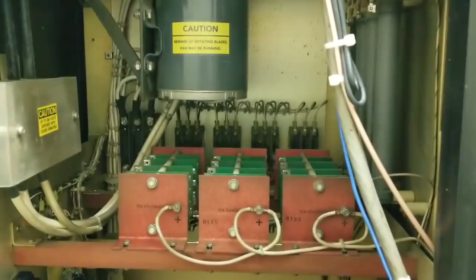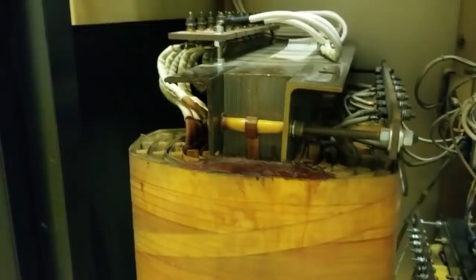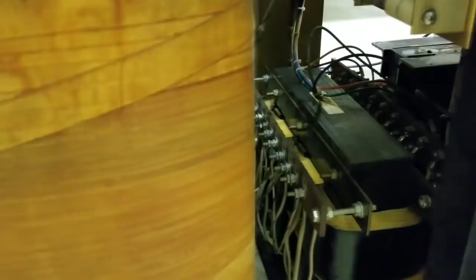Let's take a look at some of the power supply components. We usually have a rectifier stack to rectify our high voltage down for use with the tube. Right here are our three high voltage rectifier stacks for our plate voltage, running just under 9 kilovolts, and here's a 3-phase transformer that supplies that voltage. To the right of that, and much smaller, is our screen voltage supply, closer to 700 volts, also 3-phase.